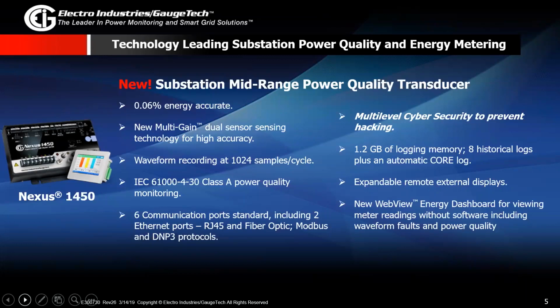And then there's another circuit which will kick in and sense your current when your load is higher and you have 5 amps or 10 amps of current. So this will make sure that your measurements are very accurate. Doesn't matter if you're using 0 to 20% of your load or you're using 90 to 100% of your load. This meter will be extremely accurate and record your energy at a 0.06% accuracy. It can do waveform recording at 1,024 samples per cycle.